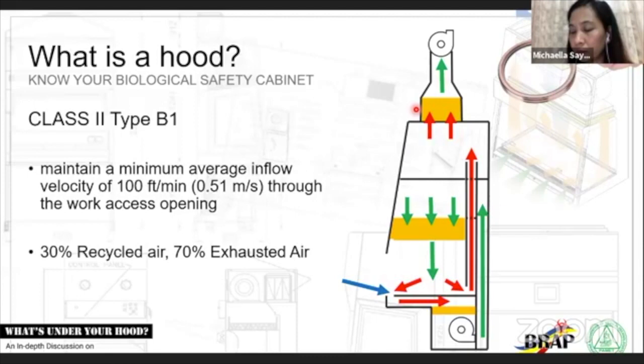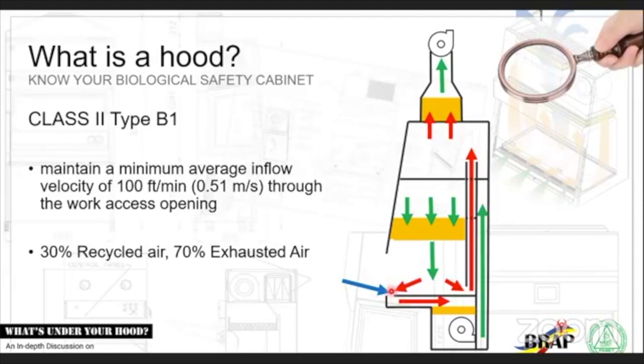Now class 2 B1. Generally all your class 2 B series are all hard ducted. So this is an illustration of that hard ducting. So you have a hard duct here and you have a blower there. So similarly to your A2, you have your air coming in. You have two slots here. However, the front grill air will get sucked by your lower blower and pushed up to this plenum. This is a positive pressure area. Then this one is connected actually to this portion. So this supplies your clean air for your chamber, okay?